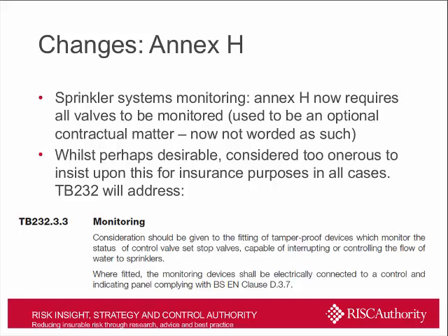Annex H in BS EN 12845, dealing with sprinkler system monitoring. So Annex H now requires all valves to be monitored, all valves that could stop the flow of water to the installations. This used to be interpreted as being an optional and contractual matter, but it's not worded in a way that allows that interpretation to be applied anymore. So again, it's possibly desirable.